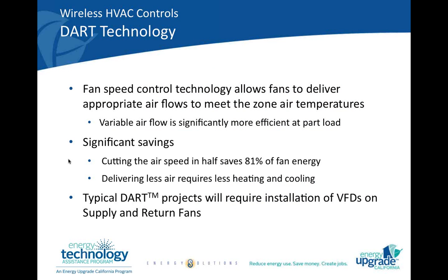So how does DART work? As I mentioned, it's a fan speed control technology that allows turn down of your central air handler fans to deliver appropriate airflows to meet the zone air temperatures. But at the same time, by running your fans at lower airflow, you're saving a significant amount of energy. Just cutting the airflow in half can save 81% of fan energy based on the way fans work.